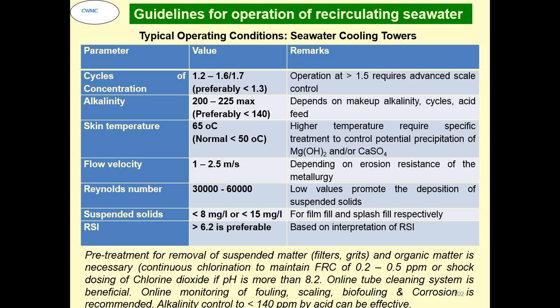Flow velocity not more than 2.5 meter per second. Of course, it will depend upon the erosion resistance of the tube metallurgy there. Something like titanium, it can go beyond 7 meter also as an erosion resistance, but then it will cause some other problems also. Reynolds number not more than 60,000. Suspended solids less than 8 ppm for film type, or less than 15 ppm for splash type fills. RSI greater than 6.2 is preferable.